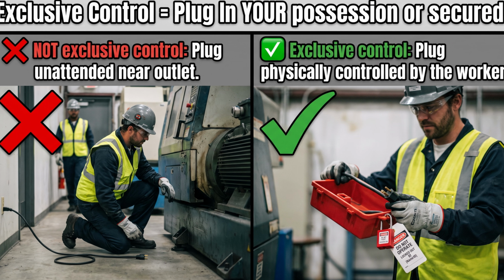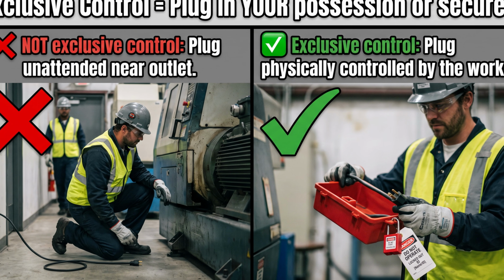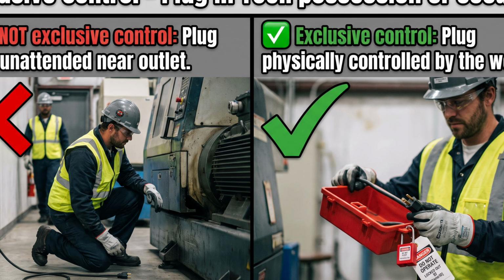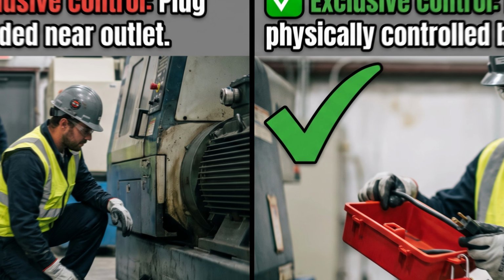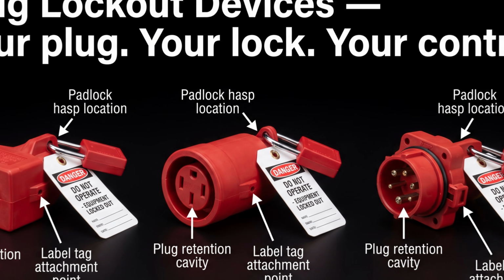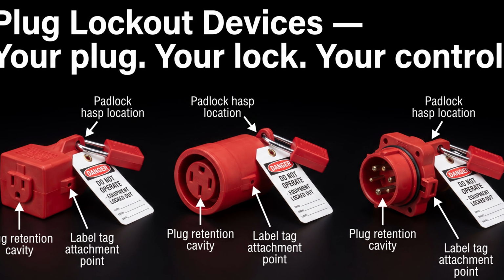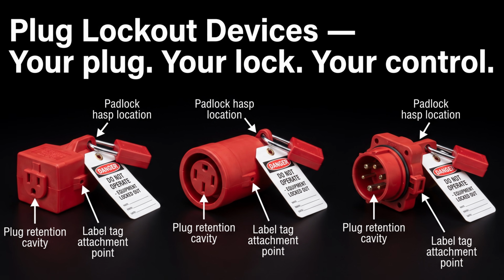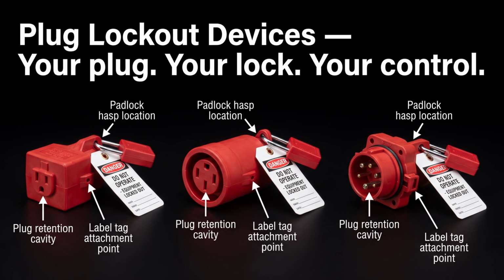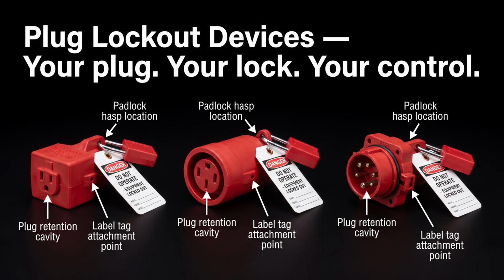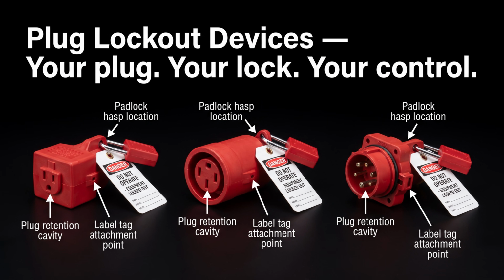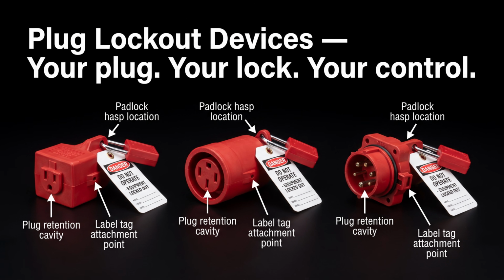The plug must be physically with you, or secured using a plug lockout device that only you control. When the plug can't stay in your hand because you need both hands for the work, a plug lockout device should be used. Plug lockouts are enclosures that fit over the plug head and accept a padlock, physically preventing the plug from being inserted into any outlet.